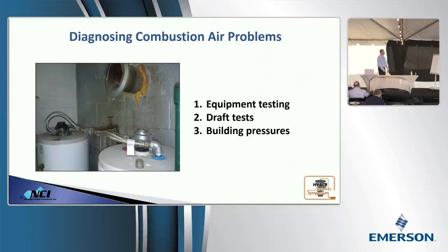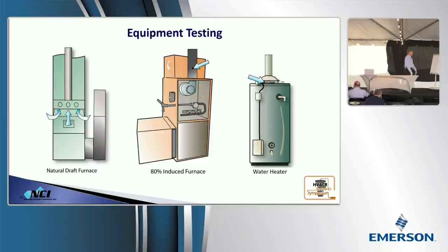Where should you test the equipment? It depends. If it has a draft hood, you need to test before that draft hood. And what we're looking for here are those three readings: CO, oxygen, and temperature. When we're dealing with combustion air issues, we are looking more at CO and oxygen. I want to know what the pattern of the CO reading and the oxygen is. If it's stable, I'm feeling pretty good. If CO's rising and oxygen's falling, completely different story.